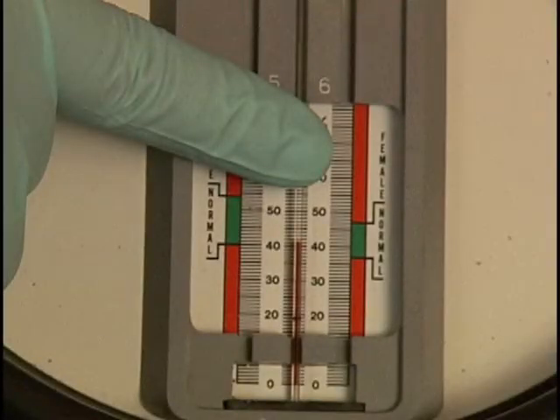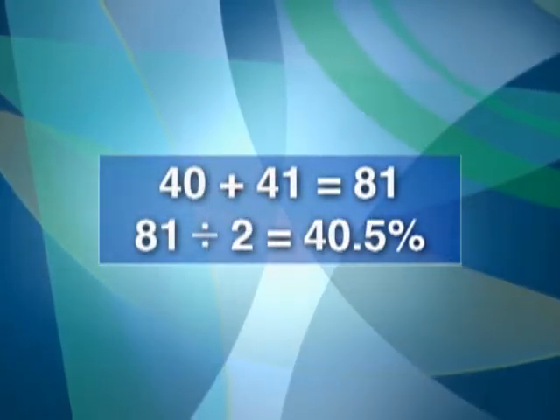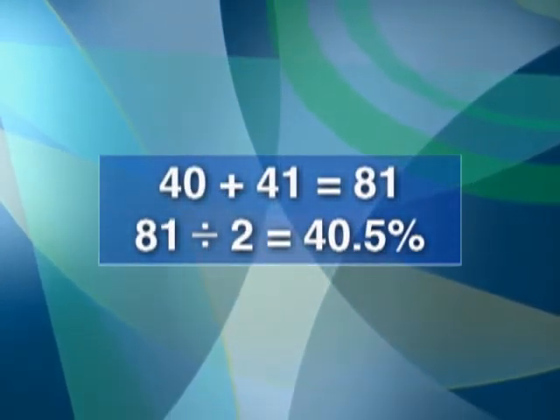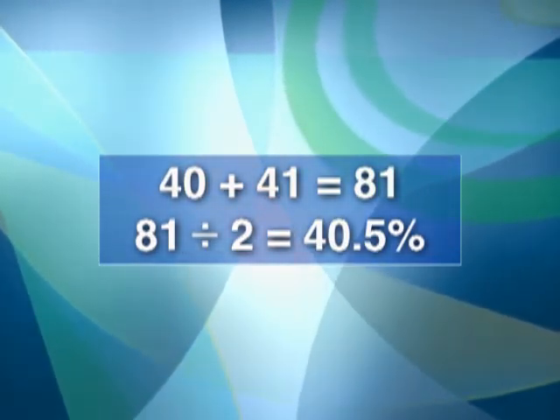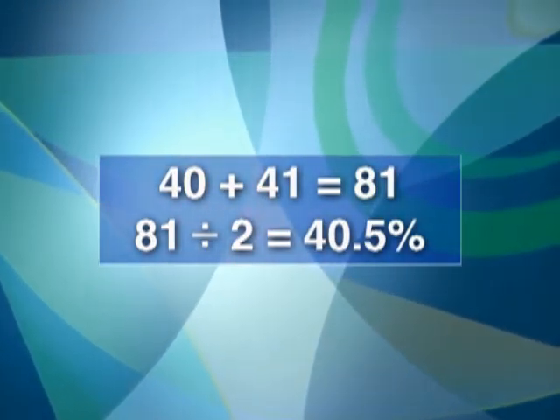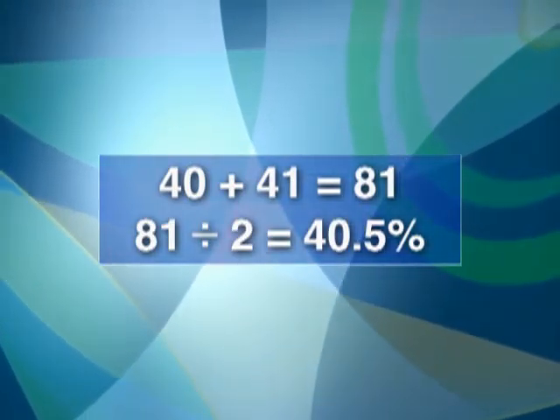Read the result of the second tube in the manner just described. The results of the tubes should agree within 4 percentage points. If not, the results are invalid, and the hematocrit procedure must be repeated. The result of the second tube is 41%. Since the first tube is 40%, the tubes agree within 4 percentage points, indicating the results are valid. Next, add the results of the two tubes together and divide by 2 to obtain the hematocrit result. The average of these two values is 40.5%.